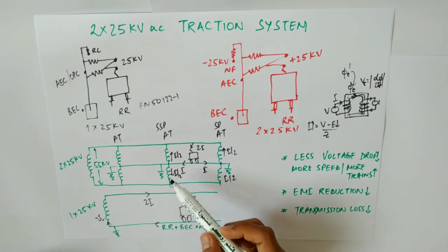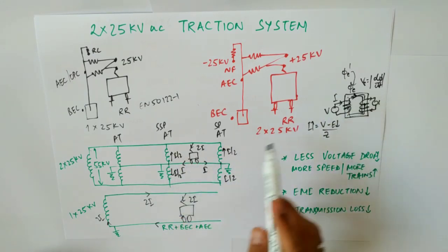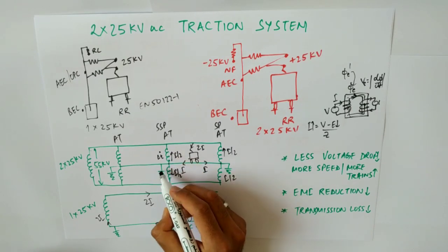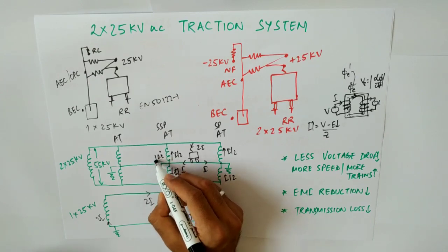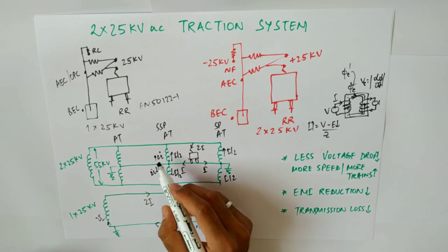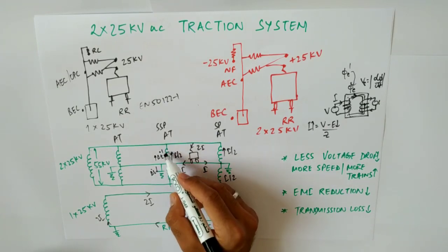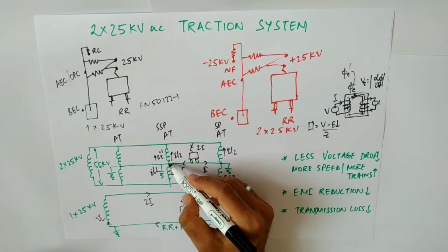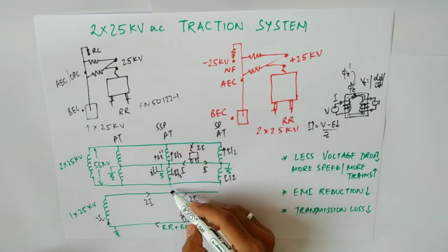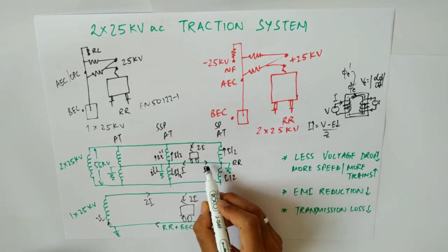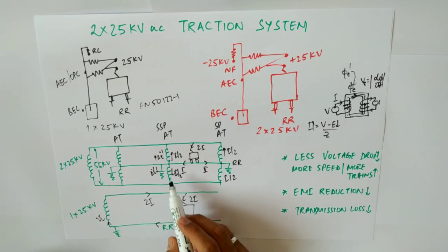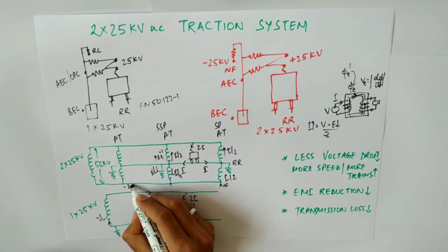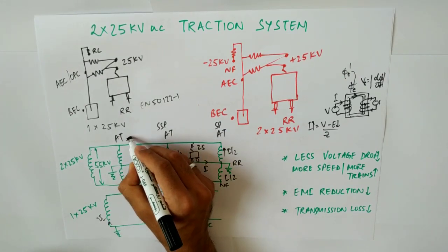In the auto transformer, when current flows into one side, a delta-I flows, and to cancel the resulting flux change, an equal current flows in the opposite direction on the other side. This process repeats until the current splits into equal halves — I/2 and I/2. The current from the running rails reaches the auto transformer, splits, goes into the auto transformer winding, and from there flows to the negative feeder at minus 27.5 kV, while the OCS is at plus 27.5 kV.